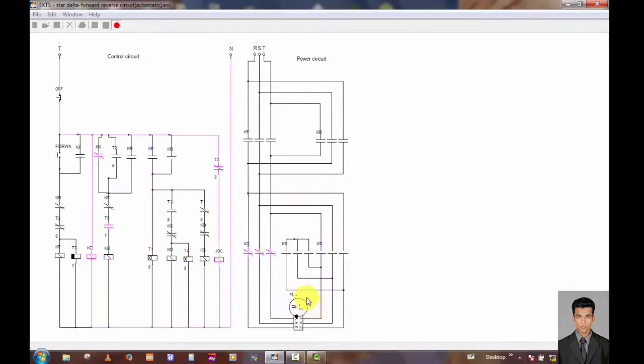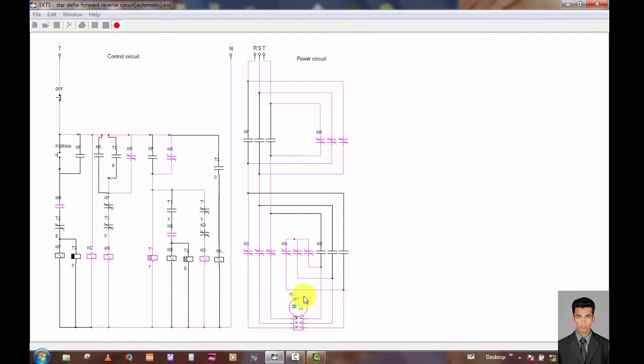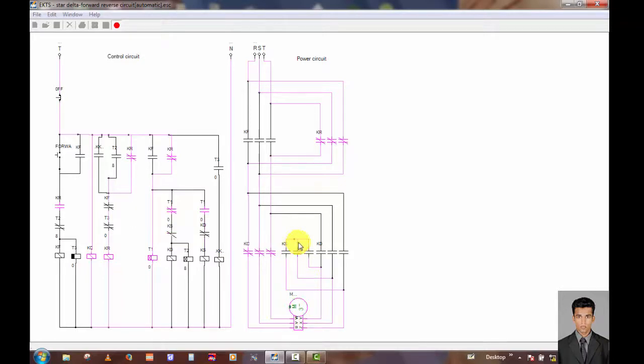This relay can stop the motor. Now the motor is stopped. This timer counts up to 1 to 8, and the motor starts in the reverse direction automatically. Now this is a Star connection; after 8 seconds the motor is transferred to the Delta system.